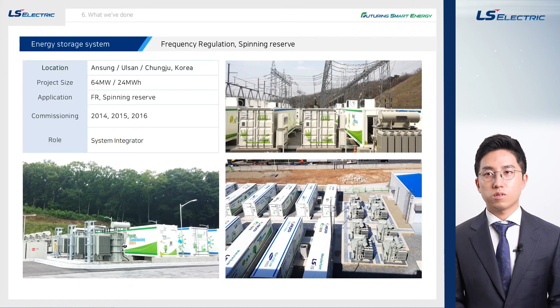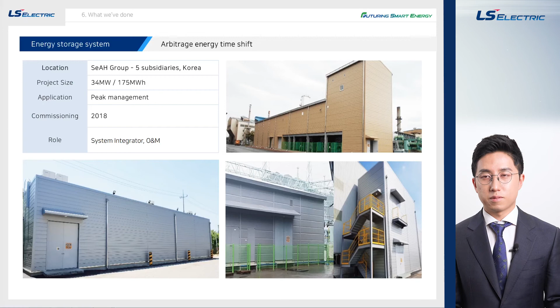This application is to manage peak power load. We installed 34 megawatt with a 175 megawatt hour ESS system in 2018. SeAH Group is one of the biggest steel manufacturing companies in Korea, so they use tons of electricity a year and use the ESS system to save on it. It charges the battery at nighttime when electricity is cheaper, and discharges and uses it in the daytime when electricity is usually expensive.